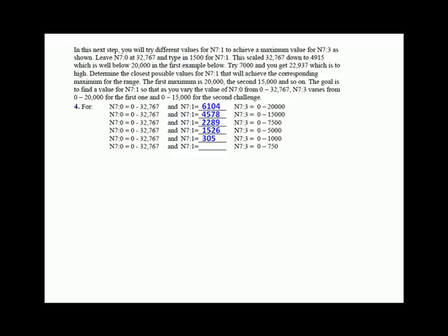The smaller the range gets, the harder it is to really nail it to a whole or a power of 10, or an even number, we'll say. And then the last one, 0 through 750, you get 229. Now, obviously, if you want 0 through 10 volts, that's not going to happen if you have a processor that doesn't support analog. But I think you get the idea of how to use a scale instruction to mathematically manipulate that raw binary value that comes in as a 16-bit signed integer and have it change in a scale or a range 0 to something else.